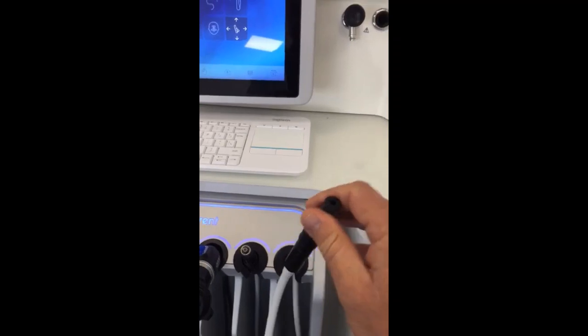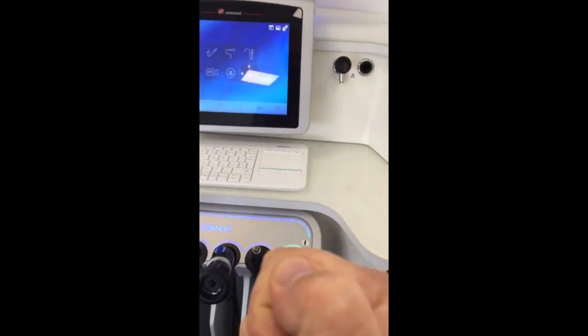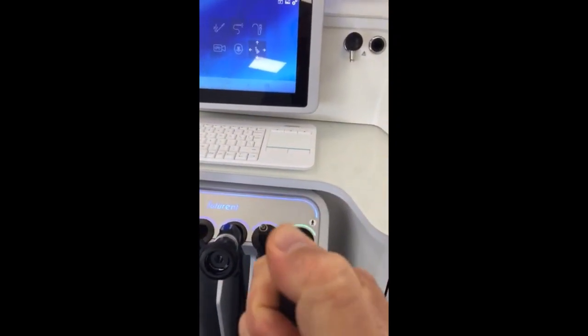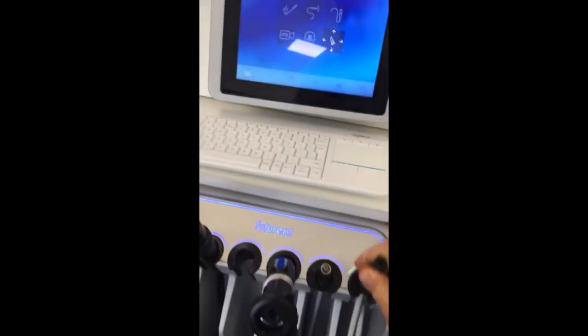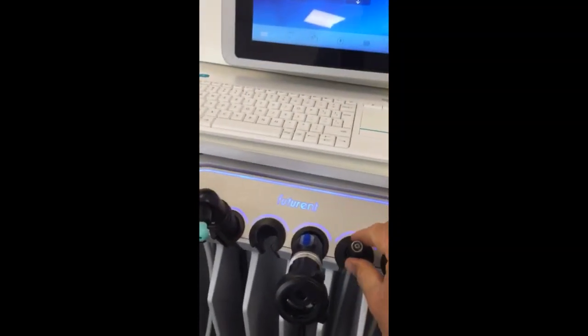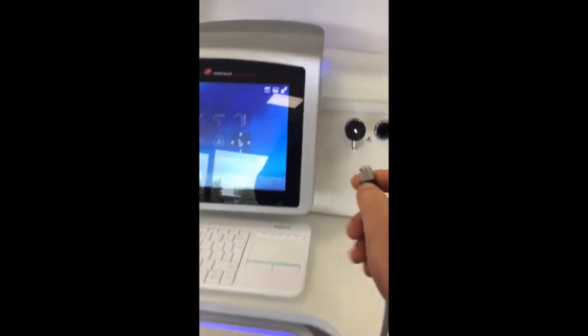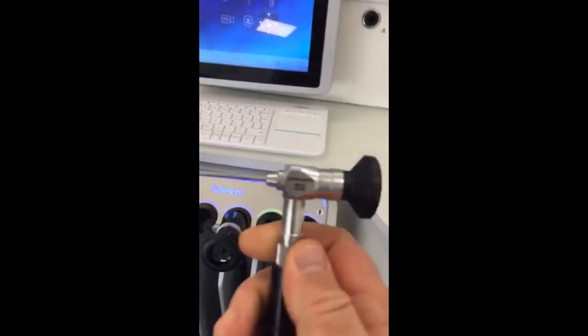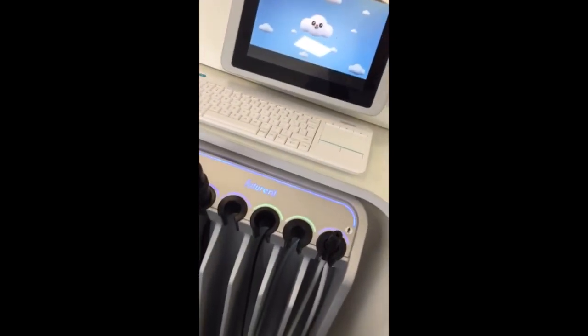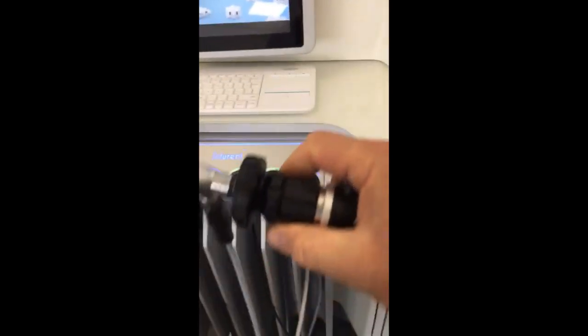This is the suction system, it starts up automatically. That's a 70-litre pump, it's very powerful. Light cable, which can be connected to the endoscope. Simply remove the endoscope, connect the cable to it, like that. And then you can click the camera onto it. Simply remove the camera from the holder, and connect it, and automatically got an image there.